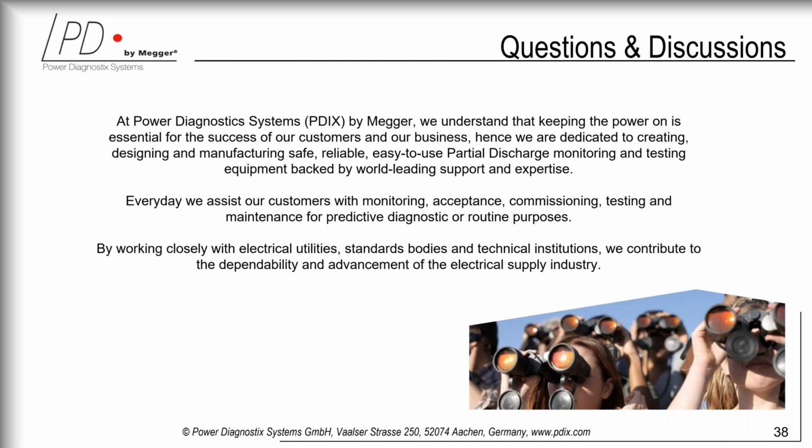For that reason, we have on the PD output a PD plus superimposed AC voltage signal, so that the second output, the plain voltage output, can be used for a tan delta measurement device. And I know customers in the US did so in the past. So yes, it's possible, and for that reason we designed this BCU2D.